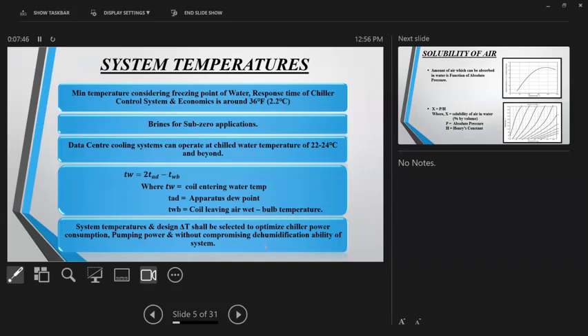And on the higher side, for data centers, you all might know that data centers nowadays operate very, very warm. So they require chill water of 20 plus, 22, 24, even 25, even 27. That's the upper range of chill waters. And obviously, if temperatures less than that are required, in the sub-zero range, obviously we use brines.